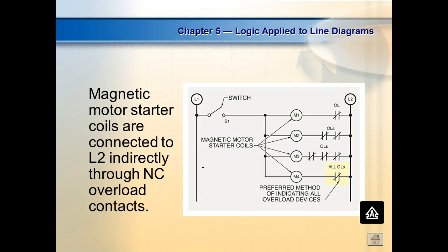And most of these are going to be multi-voltage motors. And why? Because when you wire the motor for high voltage, your overloads might be looking for 50 amps, but now you drop that down to 1/2, right? You understand? Your overload won't trip, so you have to reprogram it. So multi-voltage motors are going to have external overloads. They've got to. Because the overloads will be different depending on what voltage the motor was wired to run at.